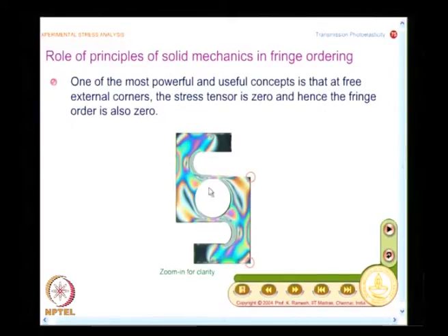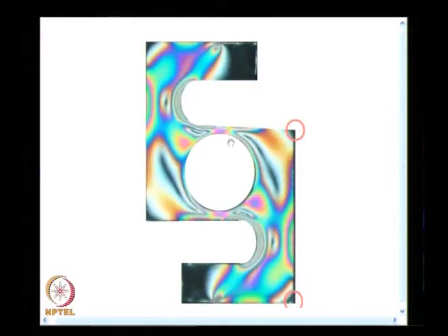I have this here, and I have this fringe field, and this is used in many popular load cell designs. This is a spring element, and they would have strain gauges put inside this boundary of the hole, and this also can be hermetically sealed. And what I have here is subject to compression along this direction and this direction, that is what you see here, and there is no load applied here.